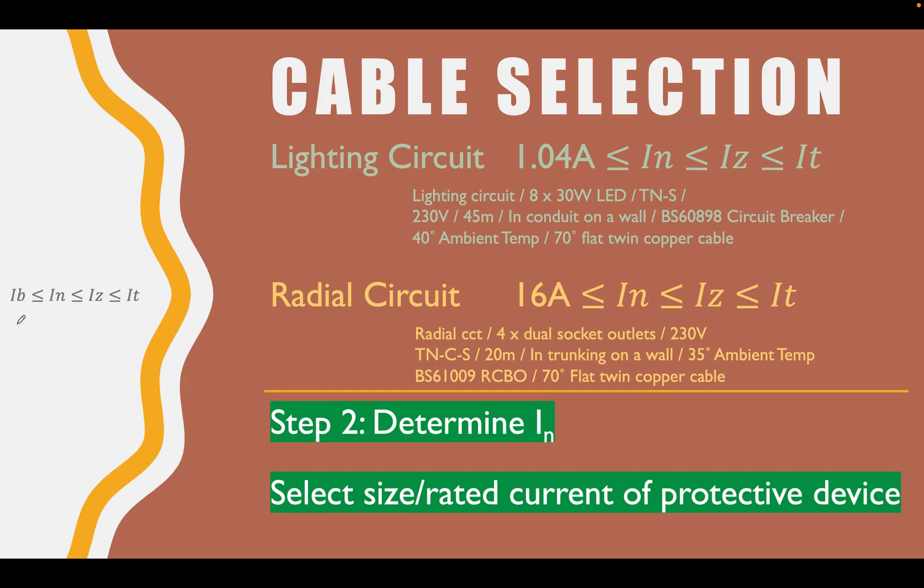Let's quickly remind ourselves what the parts of these processes are. Our IB is our design current, that was step 1. Our IN is the size of our protective device or the rated current of our protective device. IZ is the current carrying capacity of the cable in the installed conditions, and the IT is the tabulated value of the current carrying capacity of that cable.